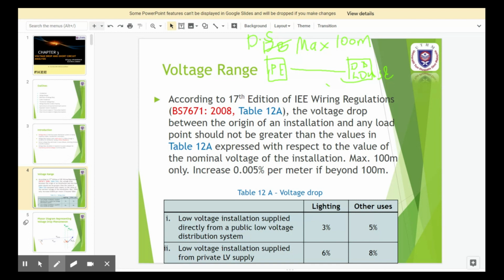so the voltage drop that you can consider for 100 meters is 3% for lighting and 5% for other uses. If your length from the distribution substation to your DB is more than 100 meters, then the allowed voltage drop increases by 0.005% per meter only. That is the regulation stated by the authorities.